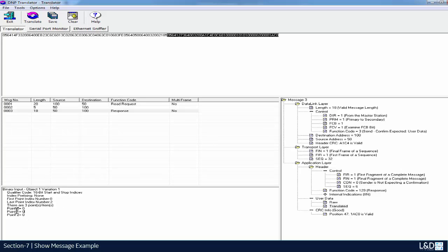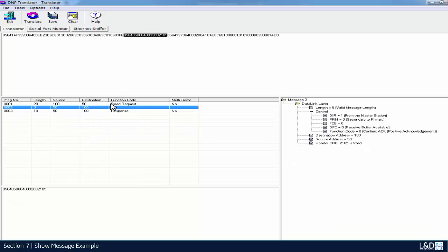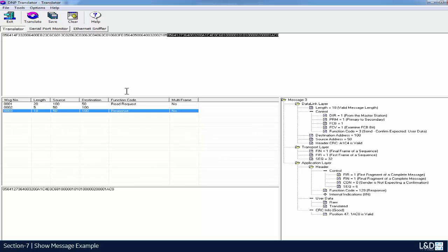One thing to note here, the naming of the points doesn't get transmitted with the message. So you have to make sure that the name or the tag name is what your operator is expecting to see in the point display in both the master and the server device. Okay, so hopefully this gave you a good understanding of what goes on between the master and the device with an acknowledgement, which is constantly repeating in a substation based on a polling duration that you pre-configure in your substation.